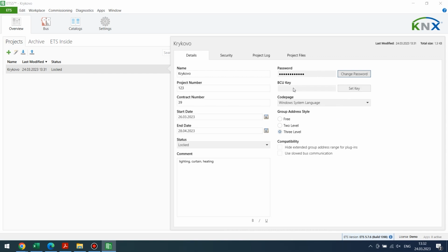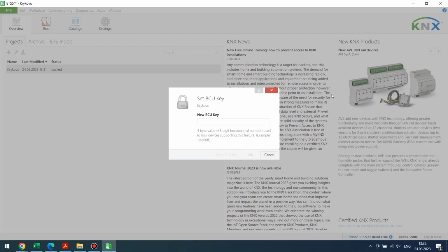The secure feature was added by the KNX Association last year to increase the security of the control system. To date, equipment manufacturers are just beginning to introduce secure technology into their devices. Not all devices support it yet. LAN connections, USB and IP gateways mainly support secure technology.